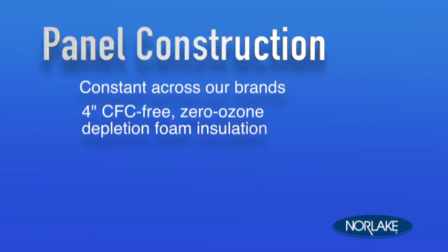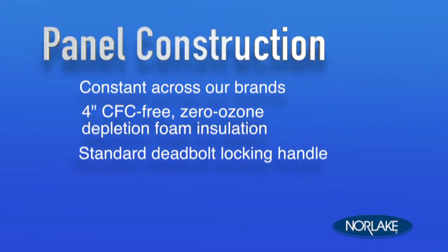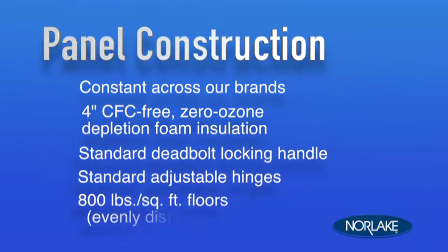Panel construction is constant across those 3 brands. We feature 4-inch thick, CFC-free, zero ozone depletion foam insulation. A deadbolt locking handle is standard. Adjustable hinges are standard. And 800 pounds per square foot floors are also standard. Please keep in mind that's evenly distributed load.